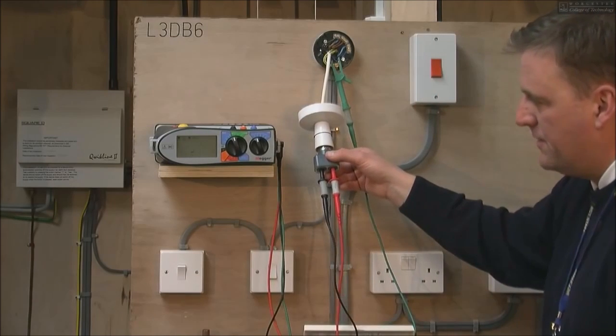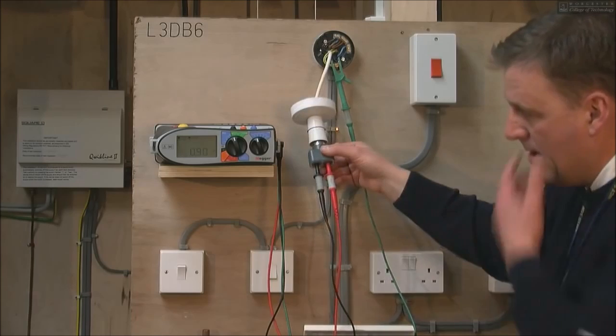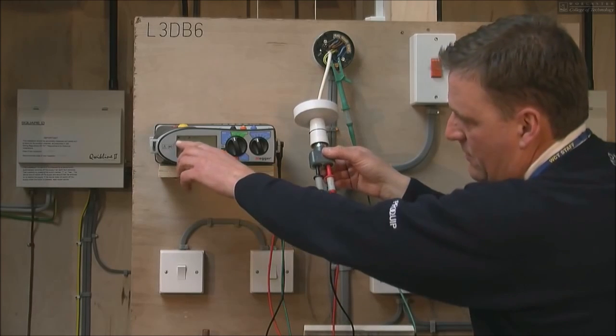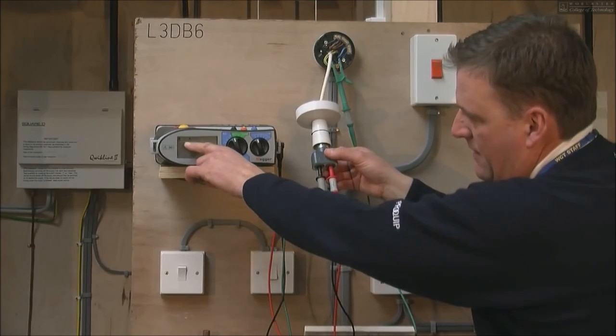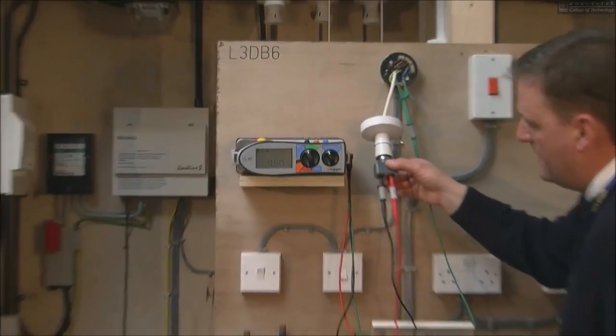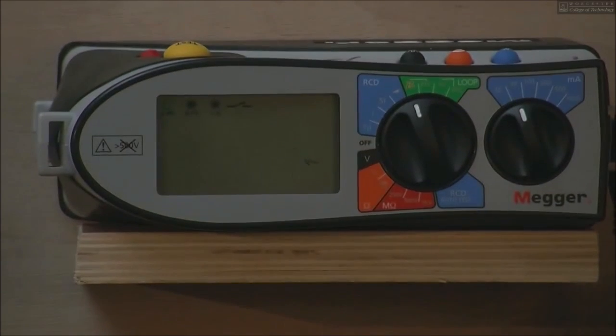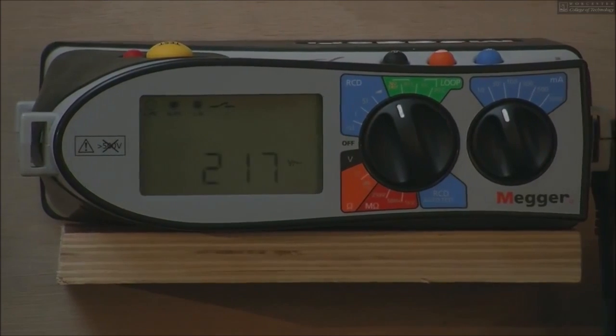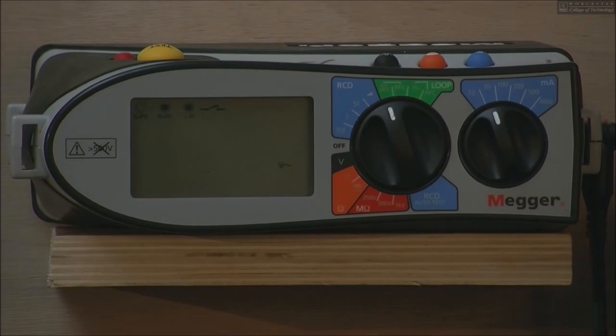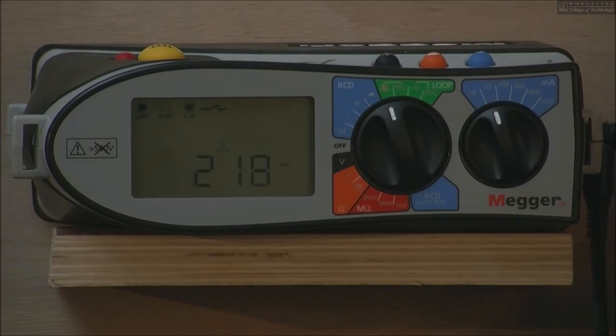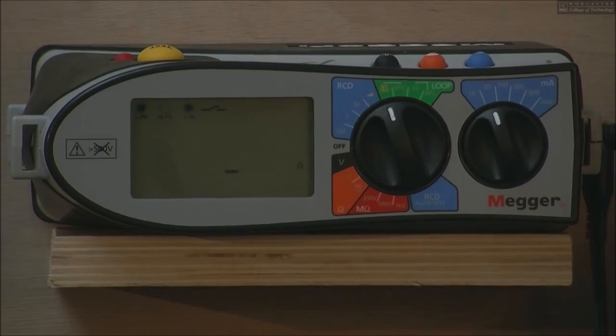Again you can test the two-way operation of your light switch. You'll also see on the test that we have correct polarity with reference to the installation. Just to prove a point, if I did get the lead round the wrong way, the tester tells you that you've got it the wrong way round. And you simply unscrew it, turn it round, and you're back to testing. And that concludes my earth loop impedance test.